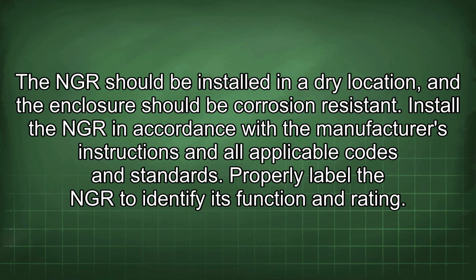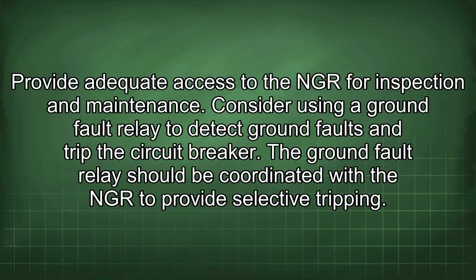Properly label the NGR to identify its function and rating. Provide adequate access to the NGR for inspection and maintenance. Consider using a ground fault relay to detect ground faults and trip the circuit breaker. The ground fault relay should be coordinated with the NGR to provide selective tripping.